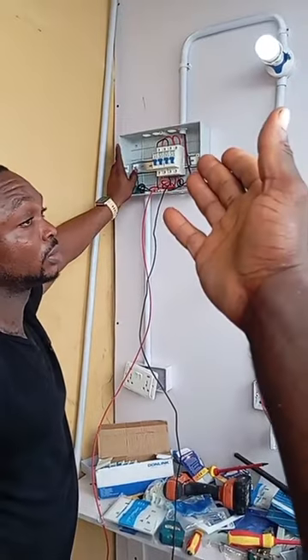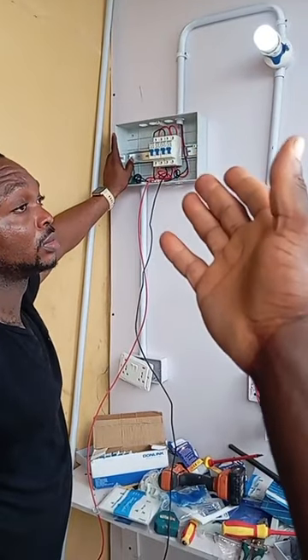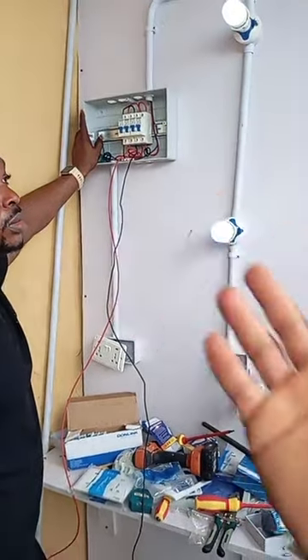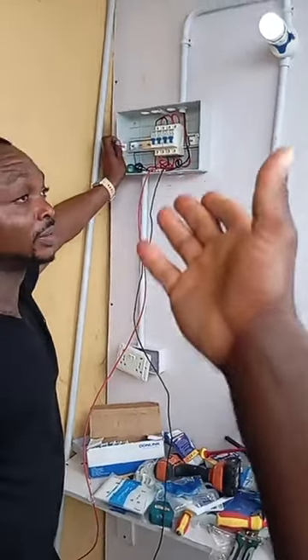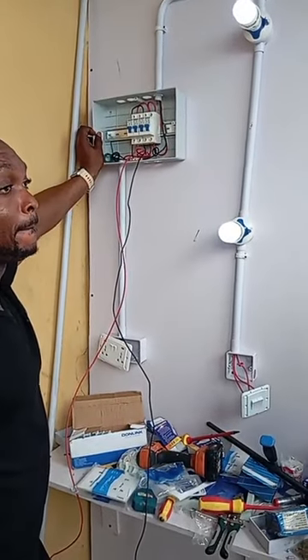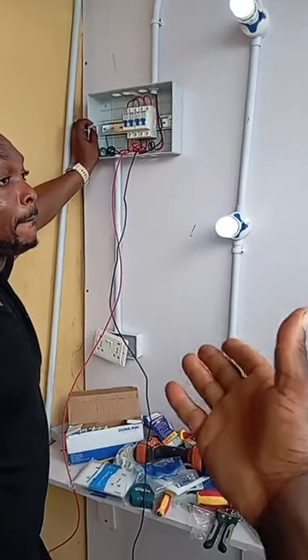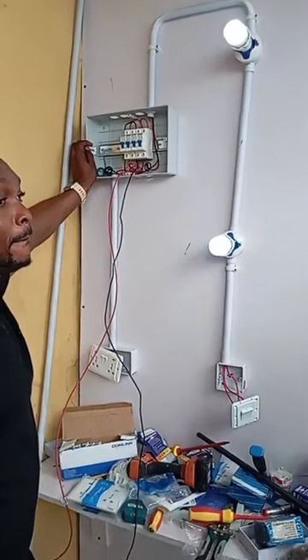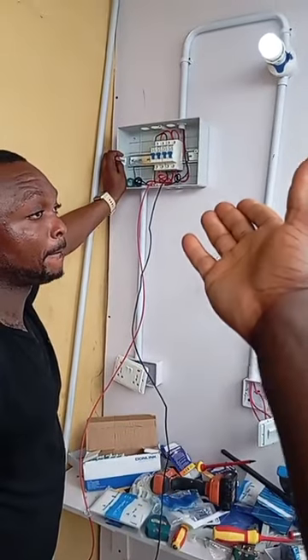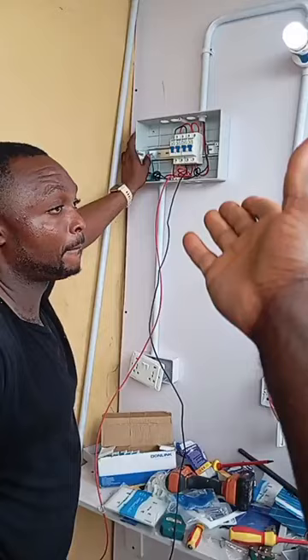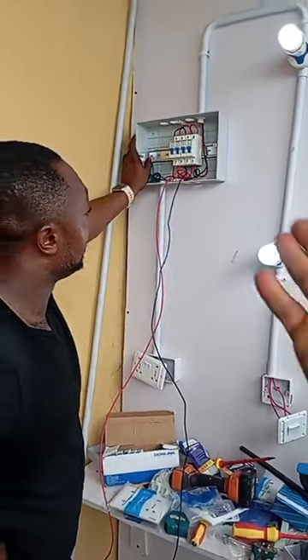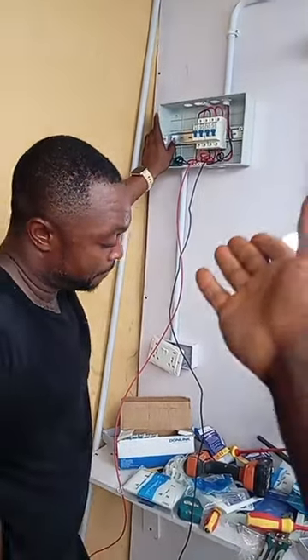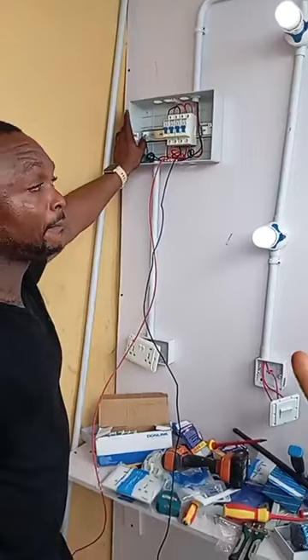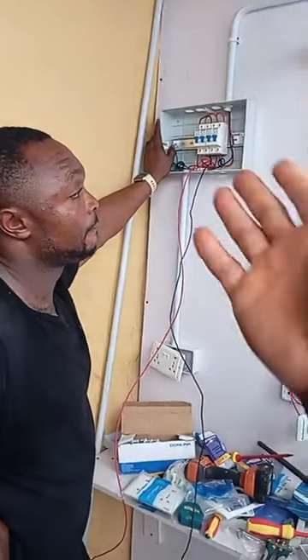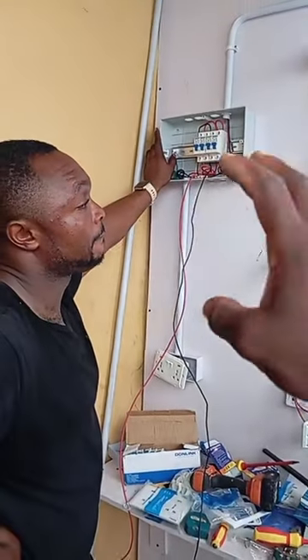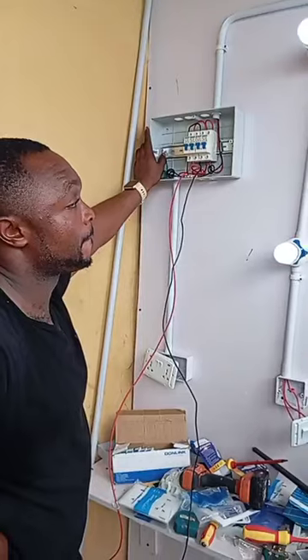But when you are using just an ordinary fan and you have a 63 amps breaker, when there is an issue in the house, the breaker will not go off because it is accepting the load that is coming inside. That's the reason so many houses go down because of wrong breaker usage in the building. If you use a 100 amps breaker on an AC that is supposed to be 32 or 63, you will discover even if the AC is catching fire, the breaker will still remain; it will not go off.